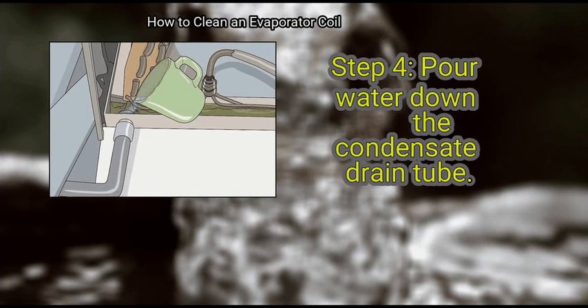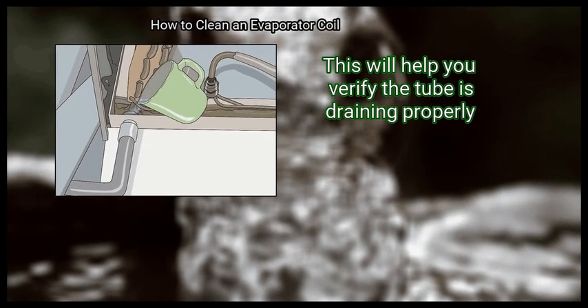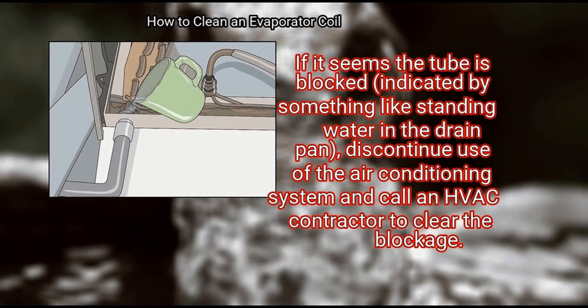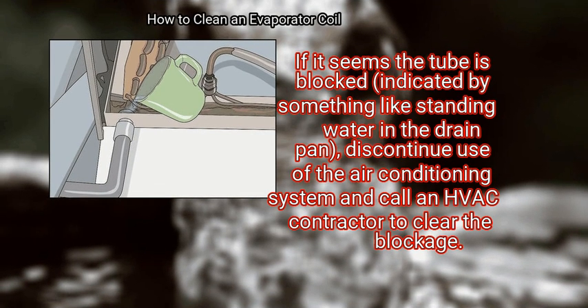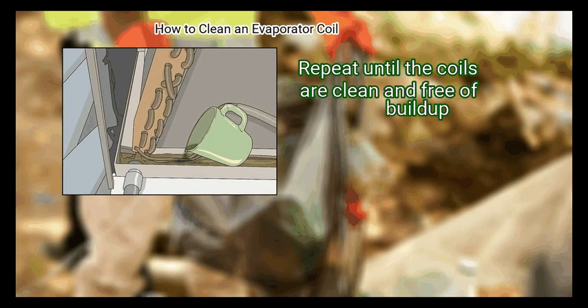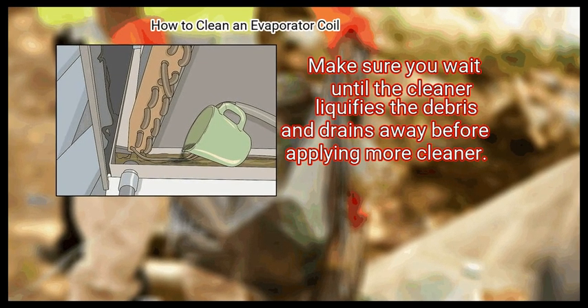Step 4. Pour water down the condensate drain tube. This tube leads away from the drain pan. This will help you verify the tube is draining properly. If it seems the tube is blocked, indicated by something like standing water in the drain pan, discontinue use of the air conditioning system and call an HVAC contractor to clear the blockage. Finally, reapply the cleaner. Repeat until the coils are clean and free of buildup. Make sure you wait until the cleaner liquefies the debris and drains away before applying more cleaner.